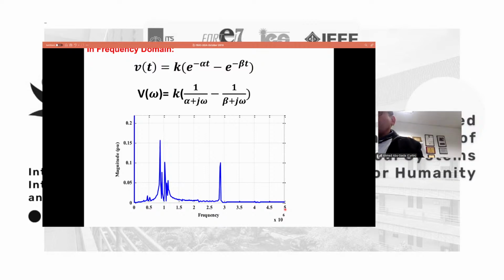Some other people, like in Indonesia, said if you don't have lightning, you may have a switching operation during a transient. If you connect a capacitor or perform load shedding, that causes a transient in the system, and during the transient you get an impulse function or wave propagating through the system, including the transformer. Can I use it to plot the FRA?